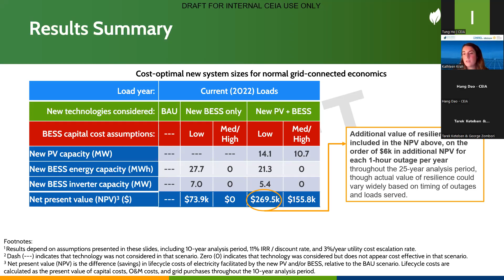This value could also vary widely based on the timing of outages and what loads are being served. This value of resilience can be considered as the cost of not having resilience - what value are you losing by not being able to sustain operations, whether that's revenue, startup costs, or salary not being utilized towards production. It could also be compared to the cost of alternative backup options, such as a diesel generator and the fuel to run it.